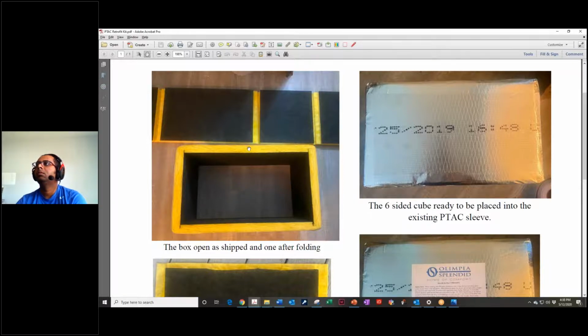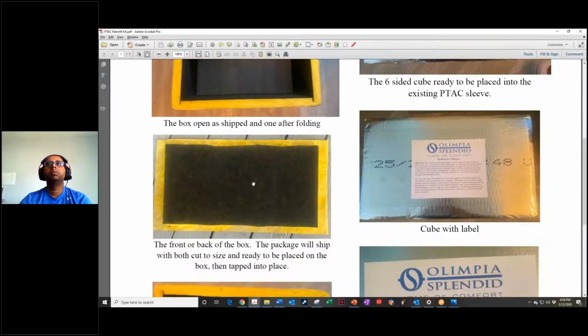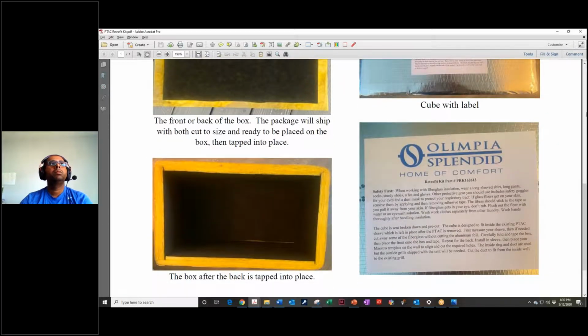This is 1.5 inch ductboard. So essentially what you have is a six-sided box with 3 inches of ductboard for sound attenuation and noise reduction, okay, and also for insulation capability. So again, it's shipped broken down, and each one will have this label that comes with it. If, let's say, your installer is not really used to ductboard, this tells them what the best safety precautions are when working with duct, and then it tells them how to put it together. And it takes, again, 10 minutes.